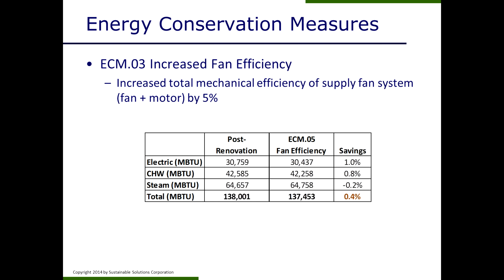But it also resulted in some chilled water savings, because within the model, it takes into account that in this particular building, the fans and the motors were located in the airstream, so they were adding heat to the air as it's flowing through the air handling units. So with a more efficient fan, we actually end up saving some chilled water, because we're reducing that heat addition to the airstream. Those are just some examples of energy conservation measures that we can look at in a model, and it's really nice because when we're looking at the fan efficiency, we're not just looking at the actual energy used by the fan, we're looking at it from a whole building perspective. So it's obviously going to have an effect on chilled water and steam usage as well, since that heat from the fan is being added to the supply airstream.